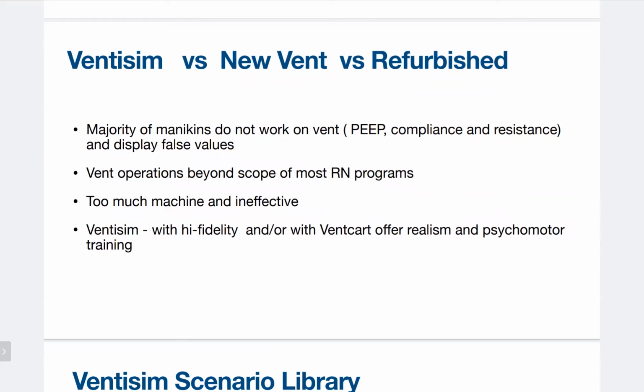And, Sally, what are you seeing in terms of the market? Yeah, so right now, ventilators are very difficult to find because so many are in use by COVID patients. I live in the state of Michigan, and we are surging right now. Hospitals are full of patients on mechanical ventilators. So trying to purchase new or refurbished is very, very difficult right now. Also, as I'm working with customers who have bought ventilators and are trying to use them, especially for COVID training, they're having difficulty connecting the ventilators to the compressed air systems. You need to have compressed air in order for your ventilators to function. And most schools do not have medical oxygen, and that throws off the oxygen sensors within the ventilators. So you cannot set your ventilator so that you have an FiO2 greater than room air at 21%. If you want to have 100% oxygen to suction your patient, you actually have to pretend to push that button, or the ventilator will alarm or even shut down.